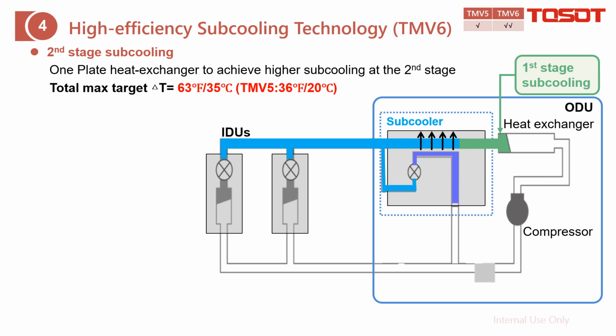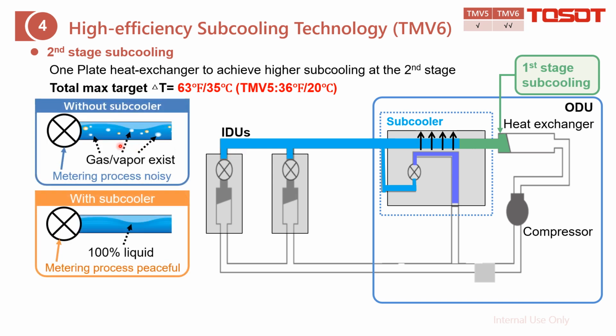The reason is that during cooling mode, we need to send the refrigerant from the outdoor unit, which is this liquid refrigerant, to the indoor unit EXV for metering. And during the metering process, we need to guarantee this liquid refrigerant is 100% liquid. The reason is that if it contains a little bit of gas or vapor, the refrigerant will make the metering process a little bit turbulent. And a little bit turbulent also means it will be noisy. And if it is 100% liquid, the process is very peaceful.